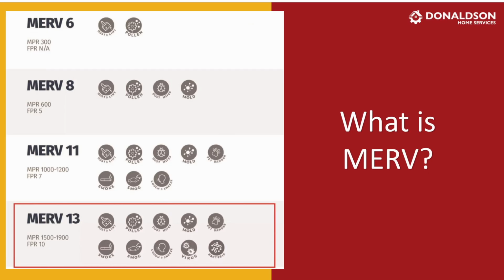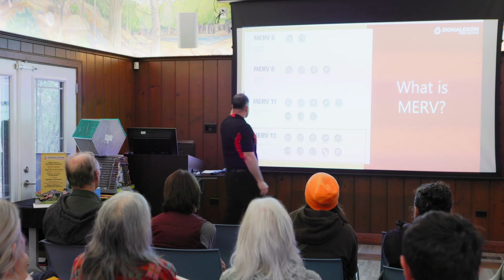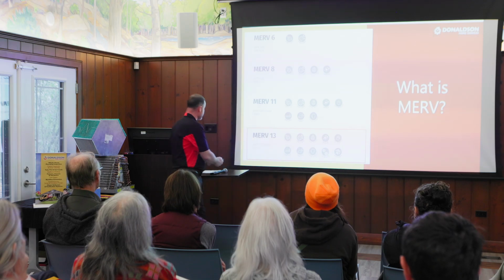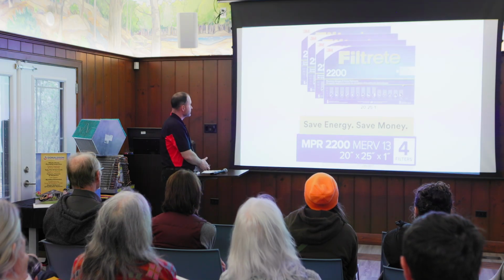You do not want to go down to a MERV 6. If you go down to a MERV 6, you're allowing a lot of the big dust, debris, all of that stuff to get into the equipment, and you're going to have issues. You do not want to go to a MERV 8, and I'm just going to actually fast forward a little bit here to this.